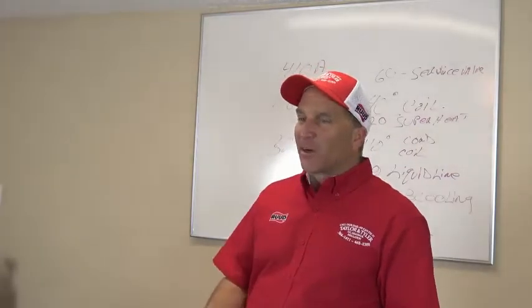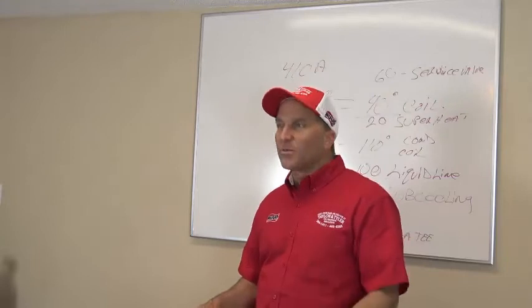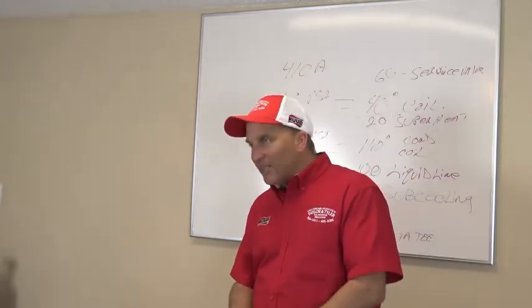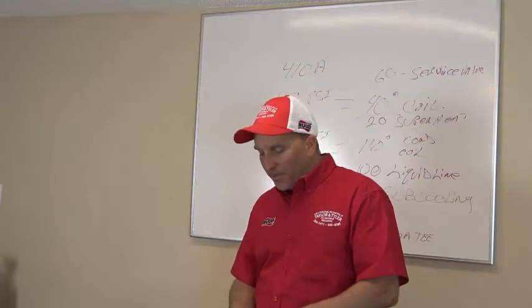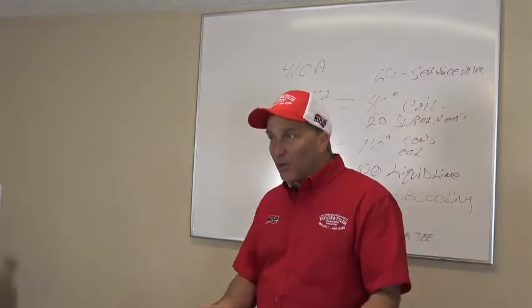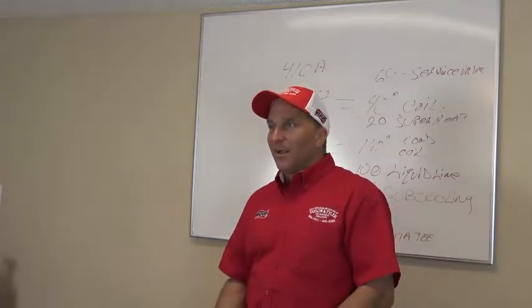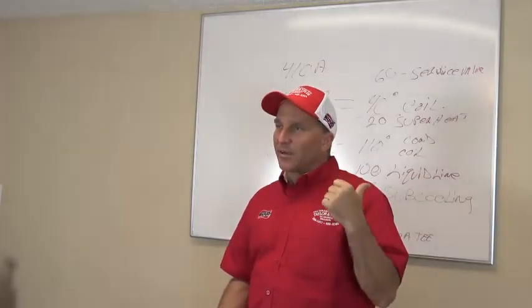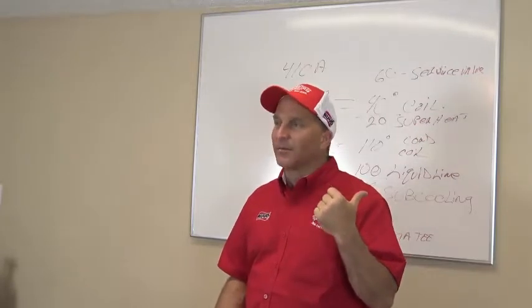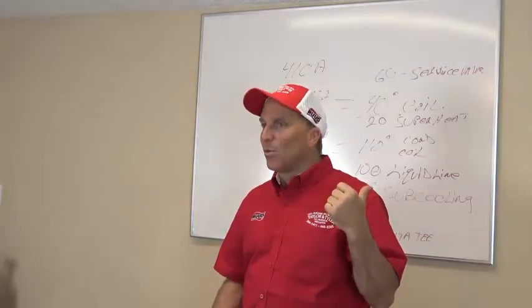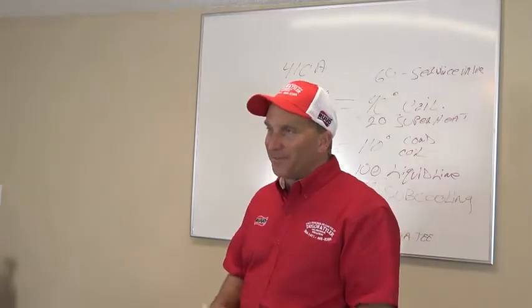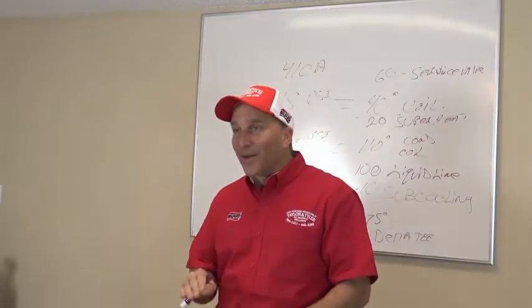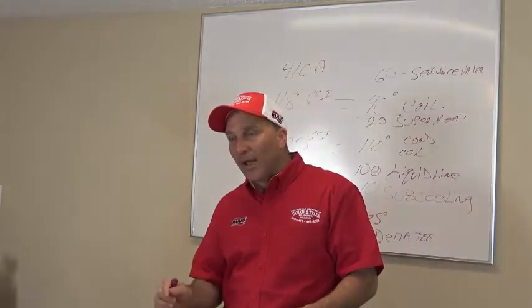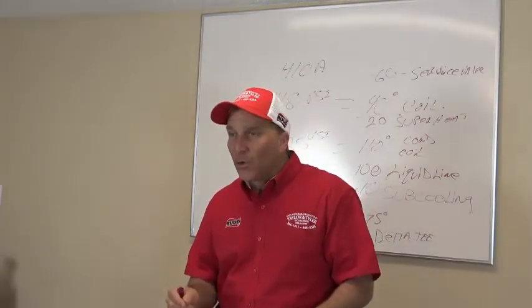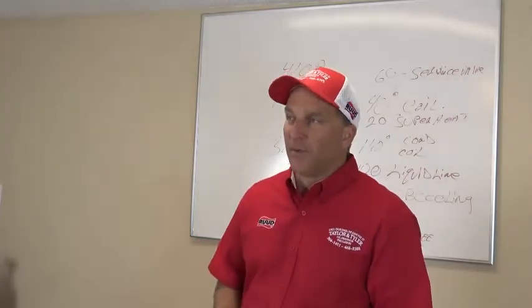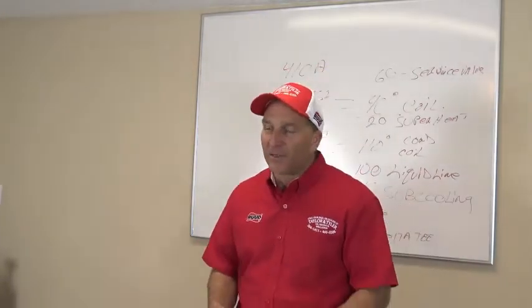So that's the first time I went and serviced the system, and I found that the compressor was bad. We had to replace the compressor. We had to replace the circuit board in the system on the outdoor unit. And when I went to do all that, and we looked at all the wiring on the system, I called him up and I said, "Dude, do you know that you got a 2-stage air conditioning system?" He goes, "Yeah, I got a 2-stage." I said, "No, you don't. You got a single stage because that's the way it's been wired since day one." He was pissed. So miswired is definitely something you need to look at. Okay? Don't assume because the system is running that it's proper. Never assume that. Never assume it.